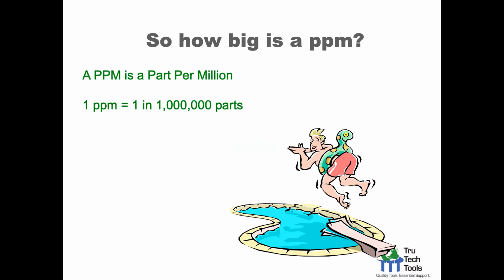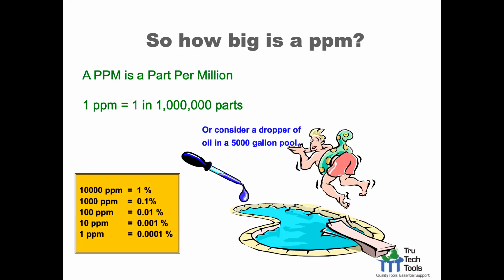So again, you probably know this from your BPI training. Combustion analysis, 1 part per million is 1 in 1 million parts. And just to give you an idea of the scope of it, it's like a dropper of oil in a 5,000 gallon pool. That's 1 part per million. That's not very much at all, but these analyzers, the detectors, the sensors are able to detect concentrations that low. So when you get down to 1 ppm, it's 1/10,000th of a percent. And then 10,000 ppm is 1%. You can see the scale on the left as things progress, just to give you an idea.